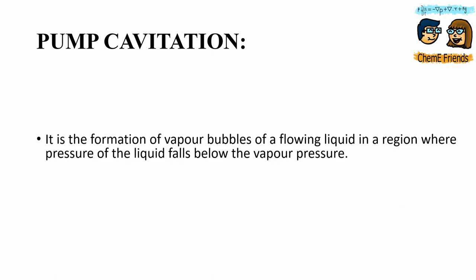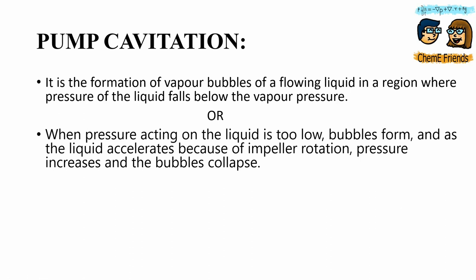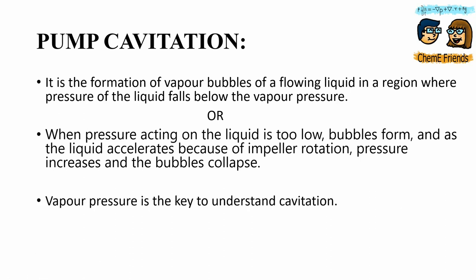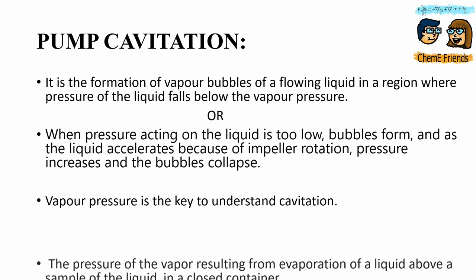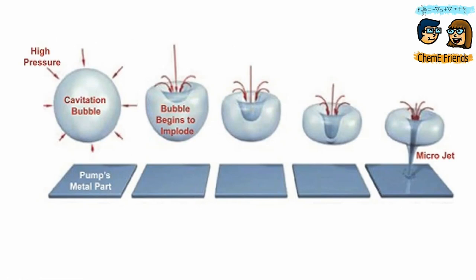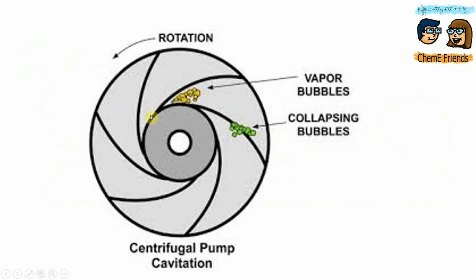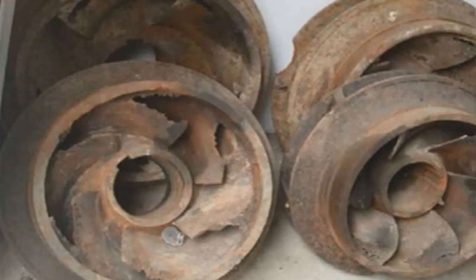At pump cavitation — the general definition says it is the formation of vapor bubbles of a flowing liquid in a region where the pressure of the liquid falls below the vapor pressure. The key word here is vapor pressure. It is the pressure resulting from the evaporation of liquid above the sample of liquid in a closed container. Consider a scenario where the temperature is high enough that it causes flashing of liquid because the pressure falls below the vapor pressure of liquid. The bubbles form at the impeller eye and are carried along the impeller vane. As they are carried along, the bubbles start bursting, and this continuous bursting causes erosion of the pump and impacts efficiency. This picture is for your reference to understand how pump cavitation destroys the pump.